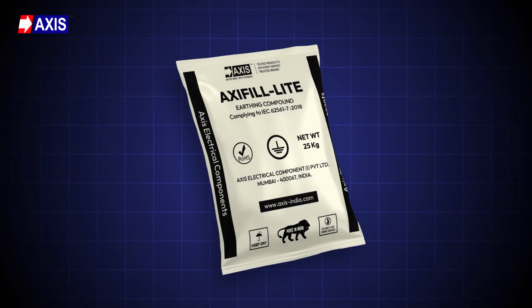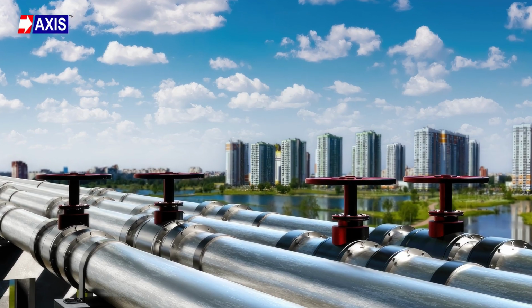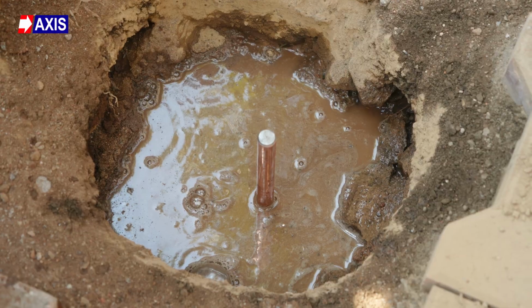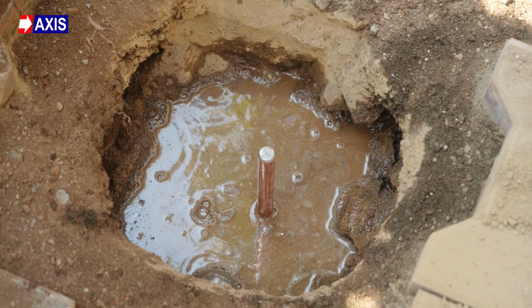Firstly, Axifill-lite. This is a bentonite-based earth enhancing compound, and it is designed for areas with high water table and moisture, typically ones closer to water bodies. When mixed with water, it swells to 13 times its dry volume, and this swelling fills air gaps around the electrode and keeps it tightly packed against the soil. This helps lower and stabilize the earth resistance.